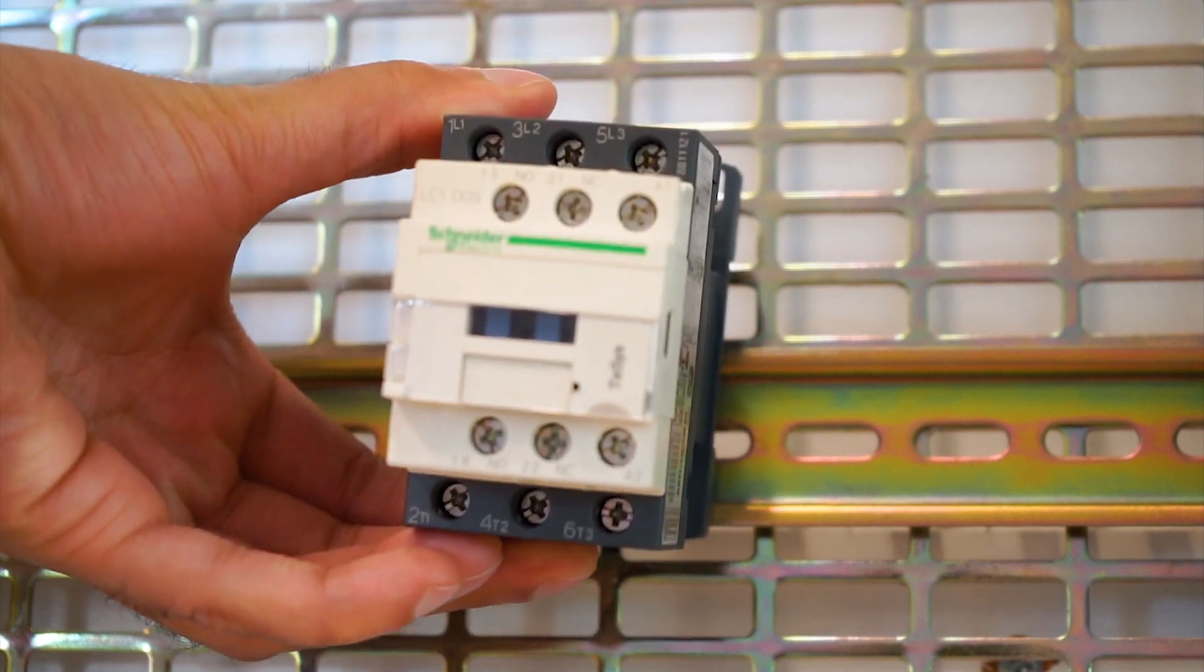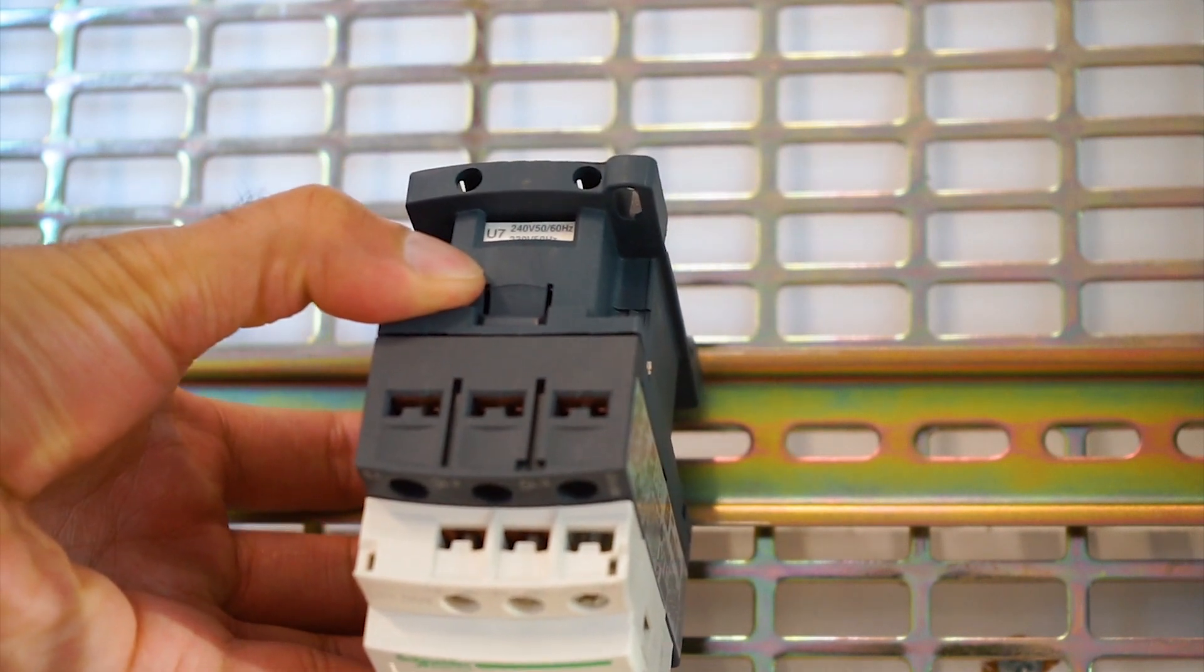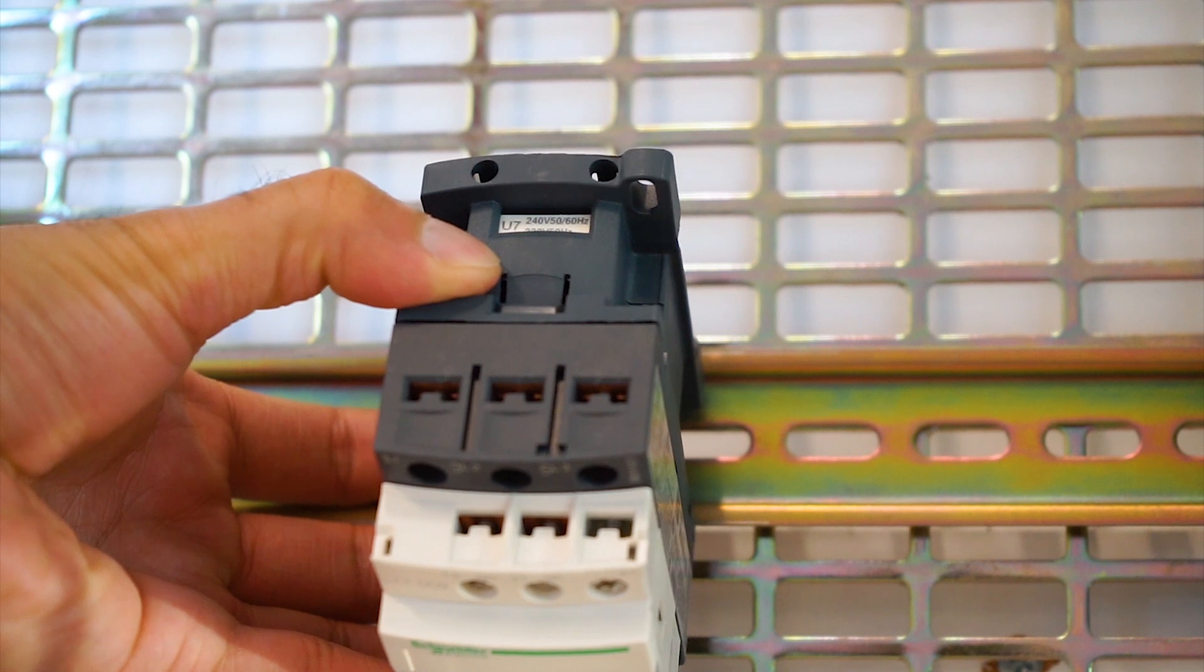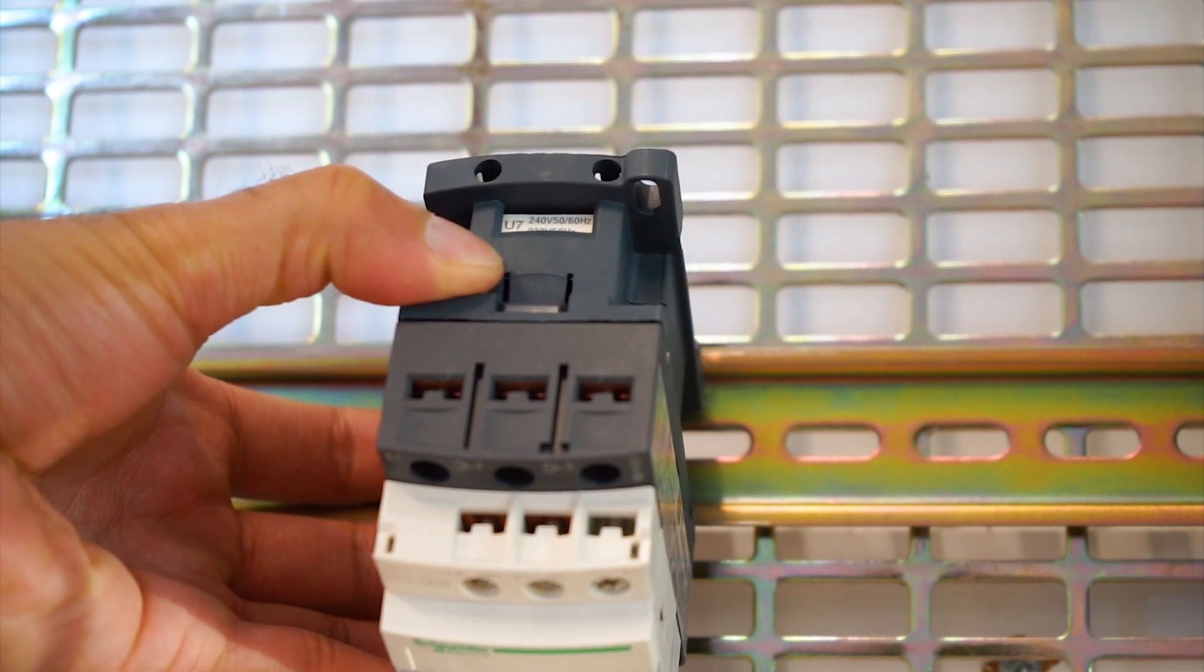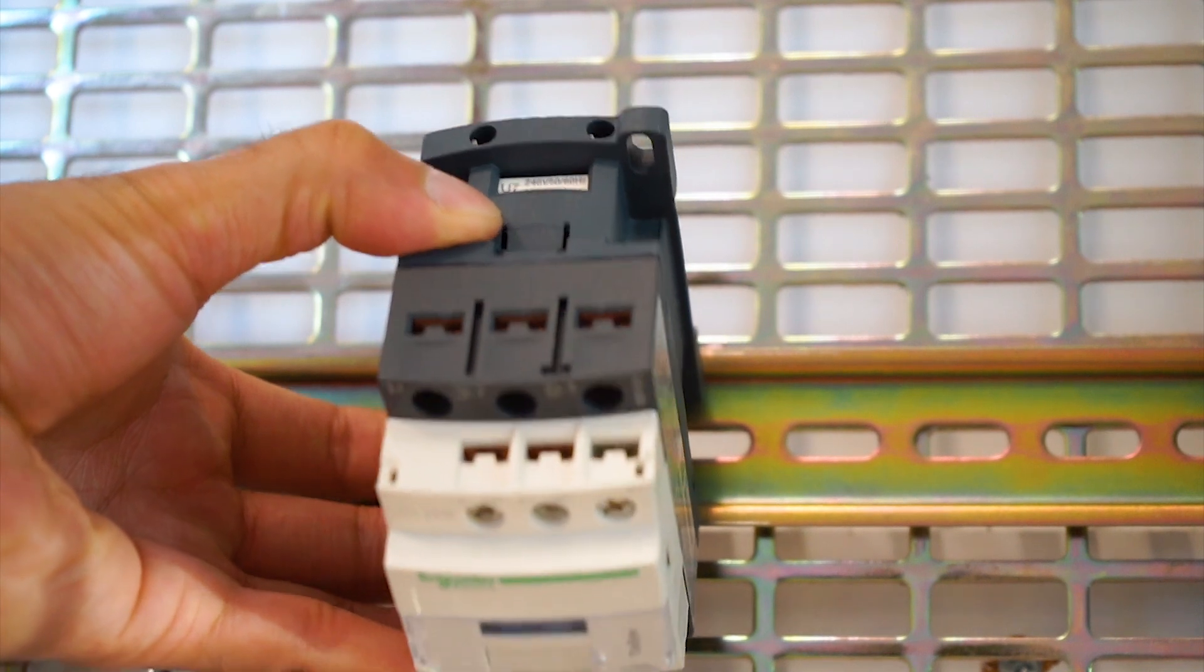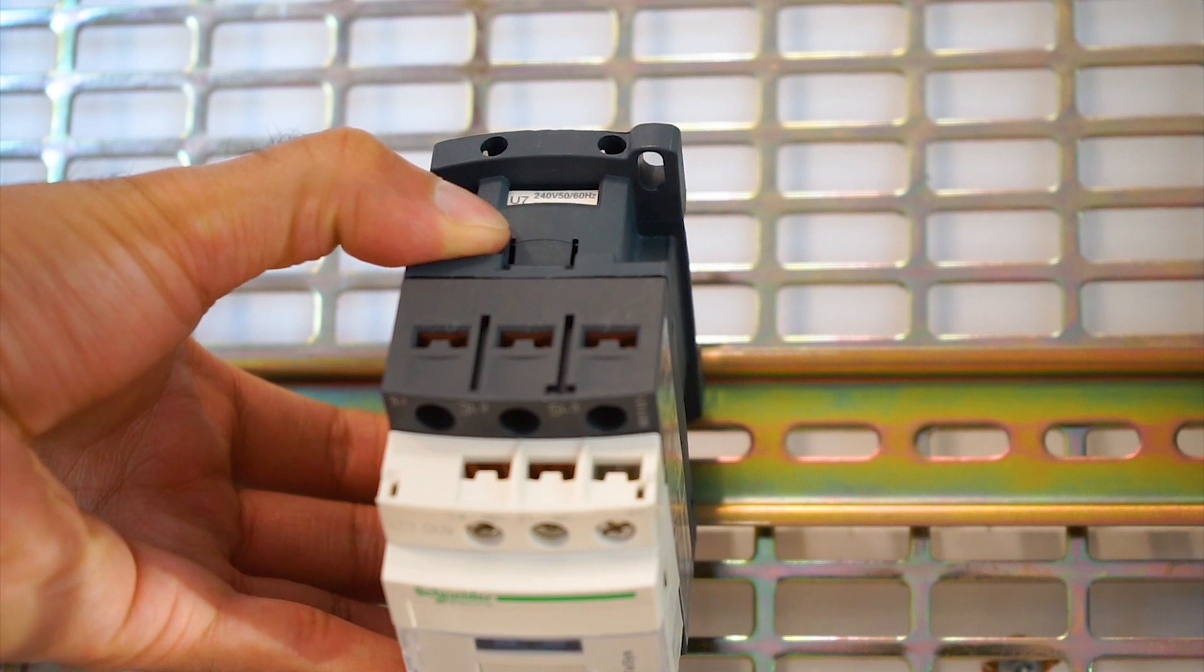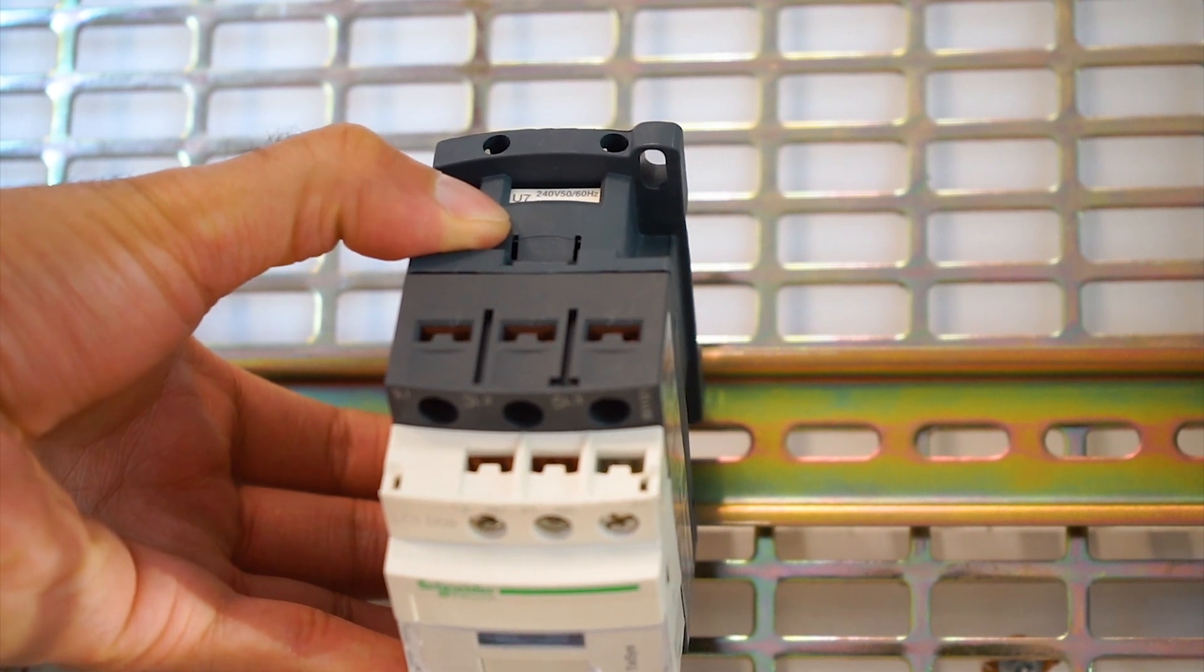You can find the coil voltage marked U7. U7 is the code for 240 volt AC coil at 50 or 60 Hertz. So that's your coil voltage for the 3-pole AC contactor. Usually you find it at the top back end.